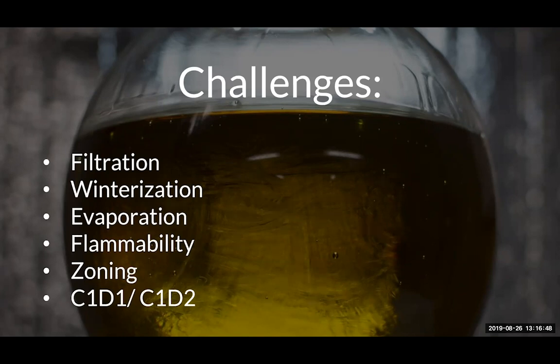That's the problem, because it's a gas, it's obviously going to be a lot more explosive. Based on the International Fire Code requirements, you'll have a lot more restrictions on how you're storing it. You have to have gas cabinets with intake filters and dedicated outtake exhaust. A lot of people, when they see flammability, just gloss over it because they don't realize how difficult implementing that is until they get into the nitty gritty of it - you can only have 240 gallons, or pounds excuse me, versus a little under 2,000 gallons.